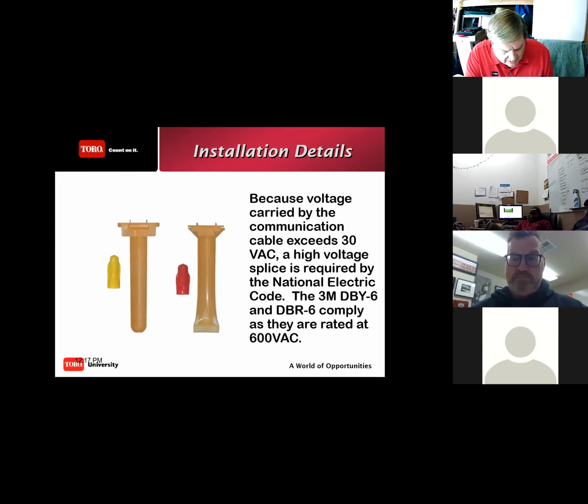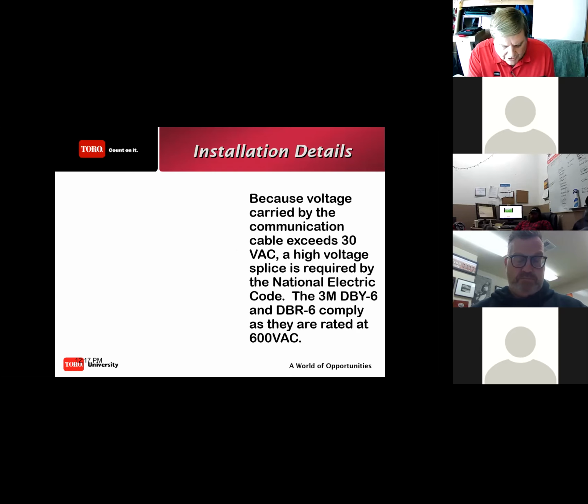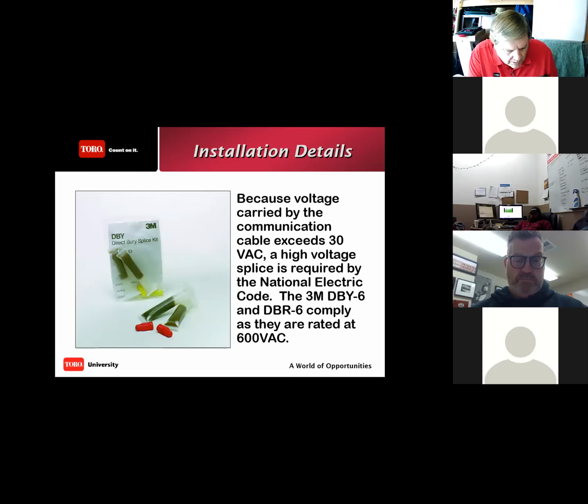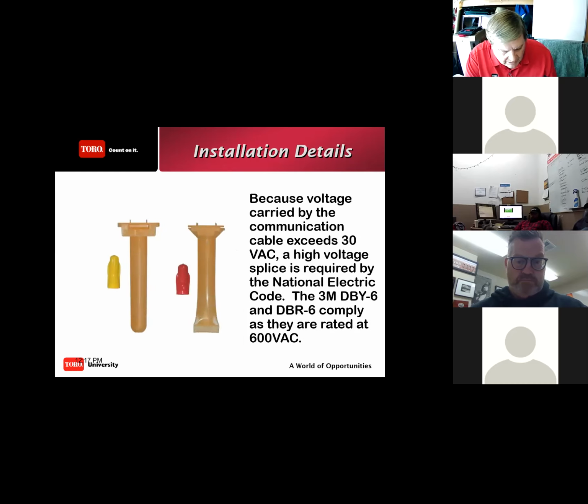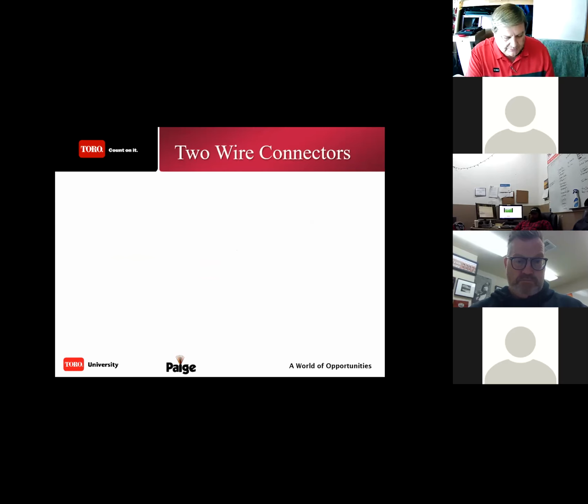So here's your standard 2-wire connection. Note the difference between the two. This is a clear or kind of a white colored connector. That's for your standard, average, everyday conventional irrigation system, 24 volt. This one here is designed for 2-wire because it's rated up to 600 volts AC. So the protectant inside the tubing is designed to handle the higher current.